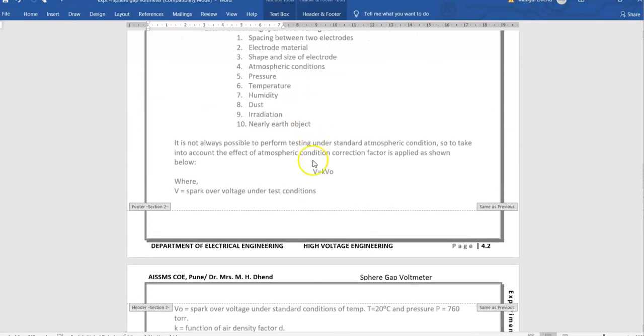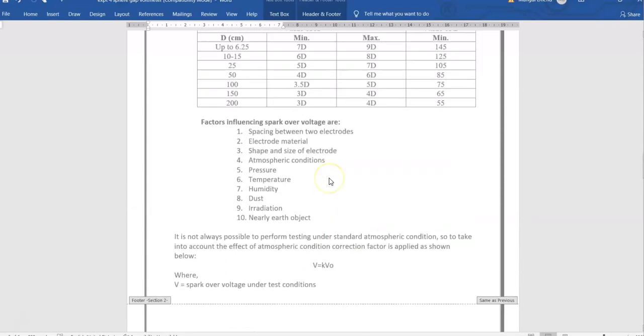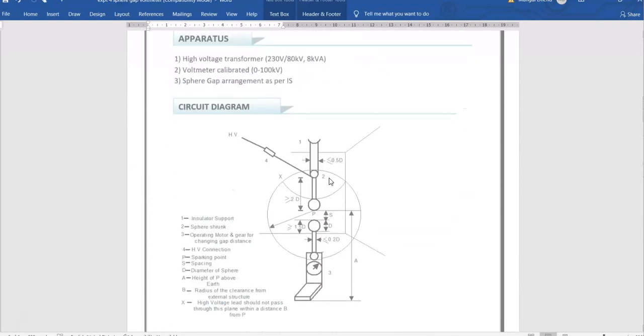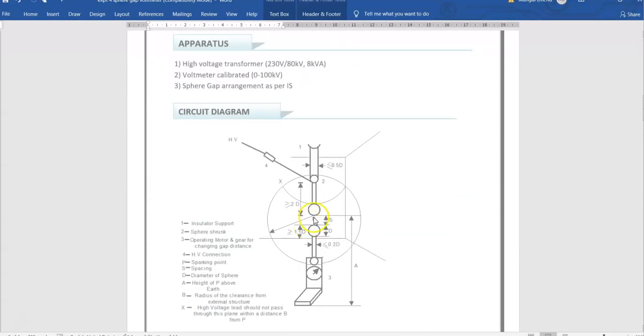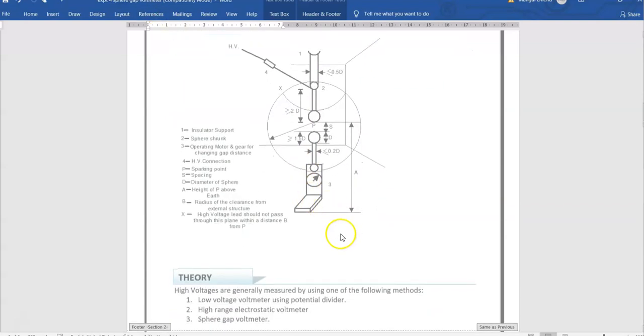Write down: voltage V is the peak value, because whatever voltage we get from the sphere gap air gap testing will be peak voltage, since spark breakdown occurs at peak voltage. But generally when we measure breakdown voltage from a voltmeter, that will be RMS. Write down, this V is peak voltage.